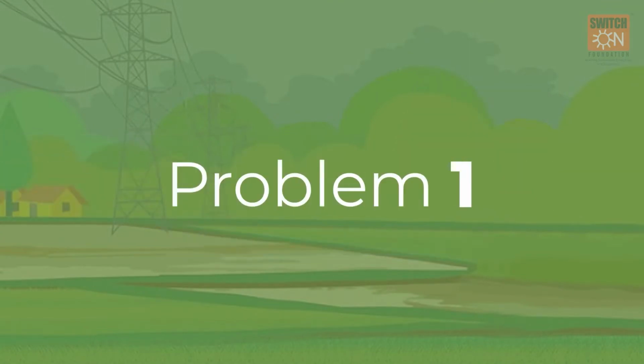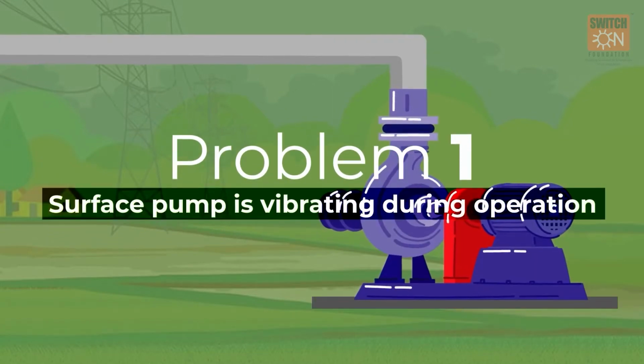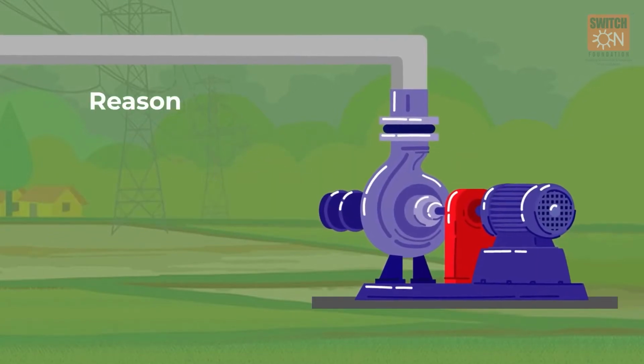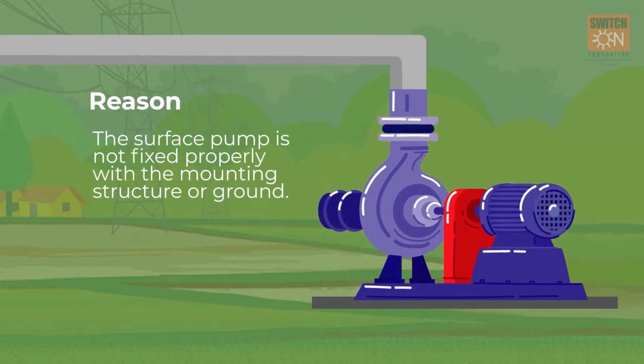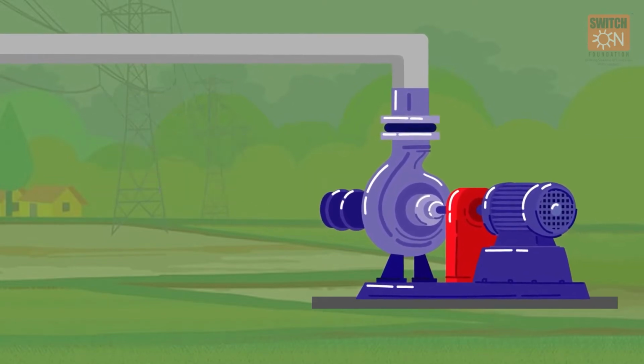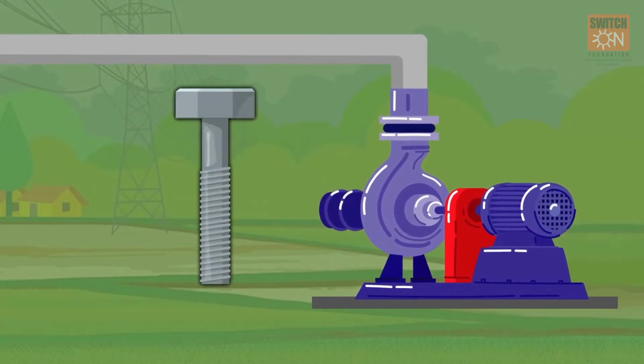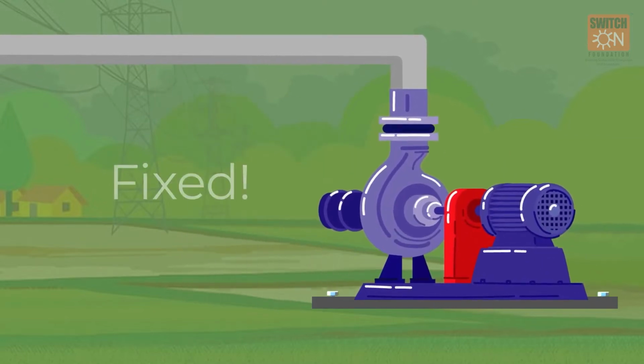Problem 1. Surface pump is vibrating during operation. Reason: the surface pump is not fixed properly with the mounting structure or ground. Solution: fix the pump using nuts and bolts and tighten the joints. Once the loose joints are fixed, then the vibration stops during pump operation.